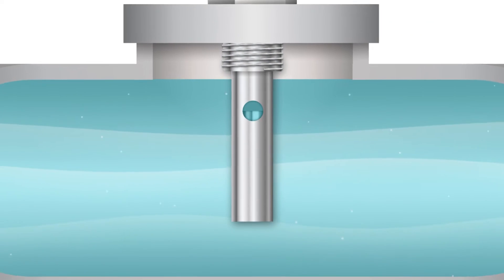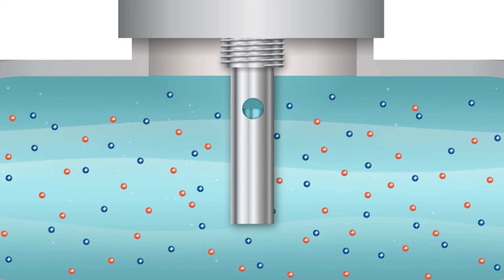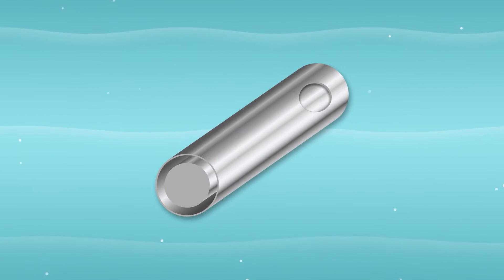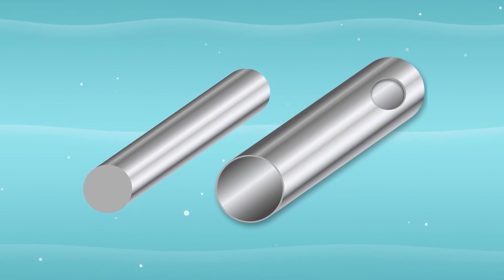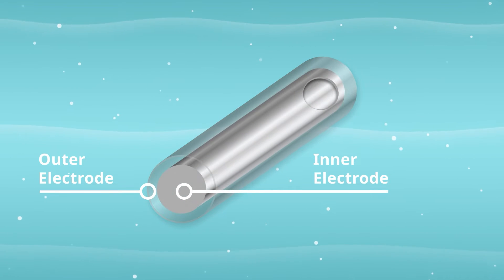The most common method for inline conductivity measurement in clean and non-corrosive water is contacting conductivity. Contacting conductivity sensors feature two electrodes that directly touch or contact the process fluid. The outer electrode is a hollow cylinder and the inner electrode is a rod made of conductive material.